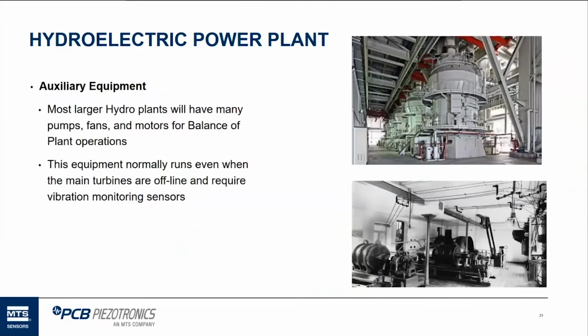Hydro plants, usually the larger ones, have some kind of balance of plant equipment: pumps, fans, motors. Those are all typically monitored for vibration to some degree, whether it's walk-around data collection or permanently mounted monitoring. We have sensors. We supply a lot of sensors to walk-around data collector companies. So if you're in a hydro plant, no matter how they monitor vibration, if they monitor it, you're going to see a PCB product of some kind.